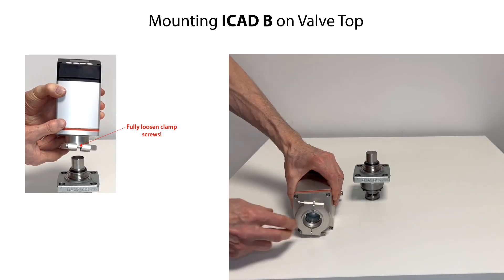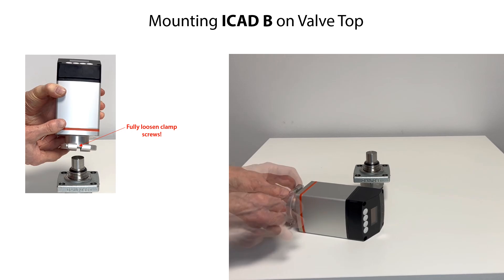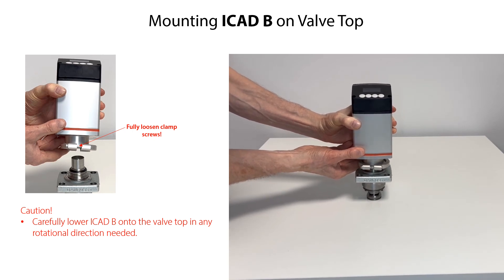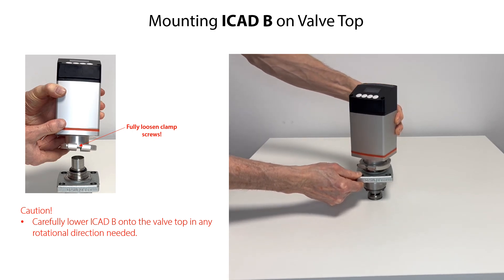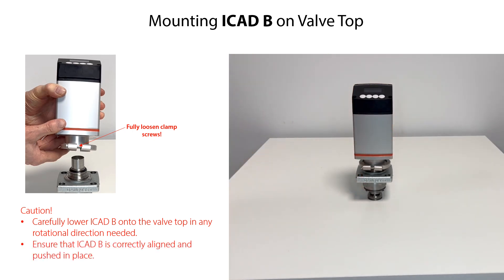Before mounting the ICAD B on the valve top, rotate the two clamp screws counterclockwise with a 3mm Allen key until they are fully loosened. Then carefully lower the ICAD B onto the valve top in any rotational direction needed. The ICAD B magnet coupling will draw the valve and ICAD B together and into position. Finally ensure that the ICAD B is correctly aligned on the valve and fully pushed in place.